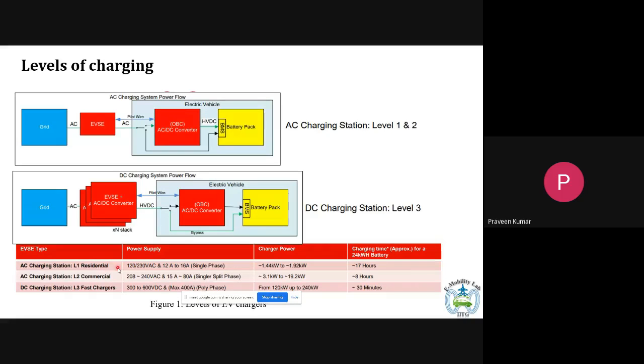Level 1 chargers are mostly used for residential applications, operating at 120 or 230 volts AC depending on the grid supply, with maximum current up to 16 amperes, usually in the range of 12 to 16 amperes, and working on single phase power supply. The power that can be drawn, depending on voltage and current rating, is around 1.4 to 2 kilowatts, which is the maximum power that can be injected into the battery.